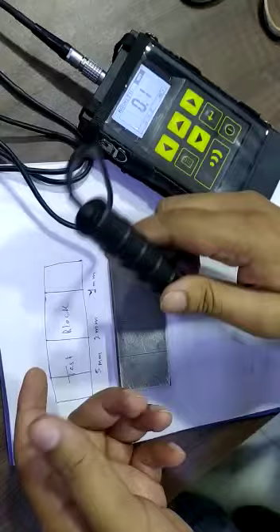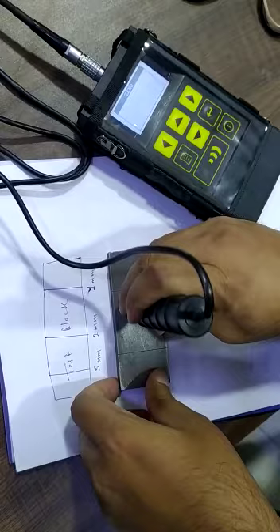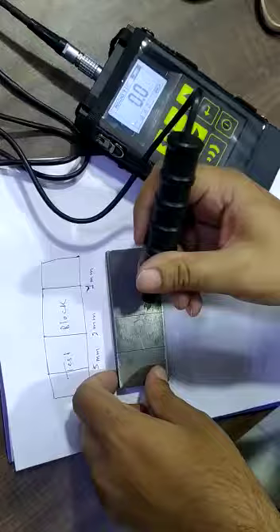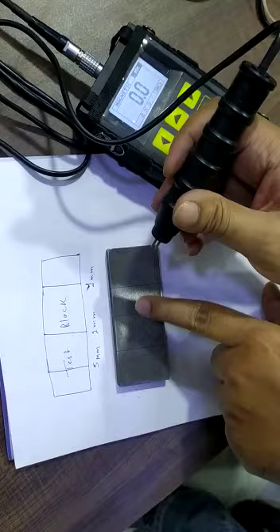It is showing 0.1, so one more time we will have to calibrate it. Again we will go to zero. We will take the reading. Some reading is coming. We will make it zero. Again we will cross-verify. Zero means zero.